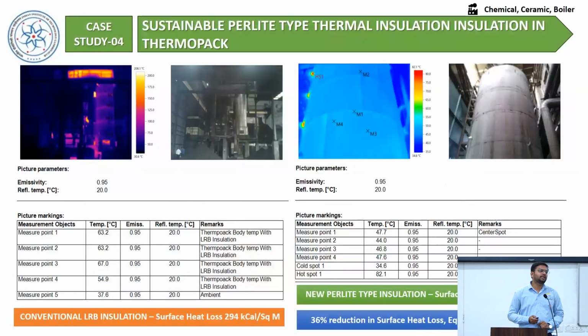Next, there are some insulation losses. The insulation conventionally used in normal practice is glass wool insulation, which is now outdated technology. Glass wool insulation has a thermal conductivity of 0.037 watt per meter degree Celsius. After a year of application, it absorbs some moisture and some dust from the atmosphere. Once the binder has evaporated from the insulation, the insulation properties are lost. In some old insulation, we can feel that it has too much heat conductivity.